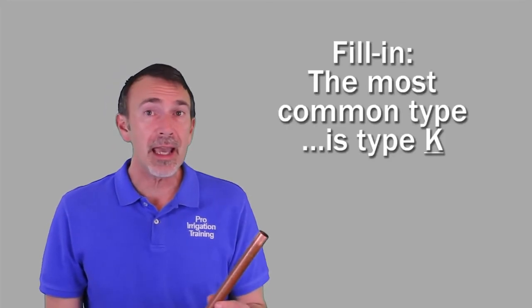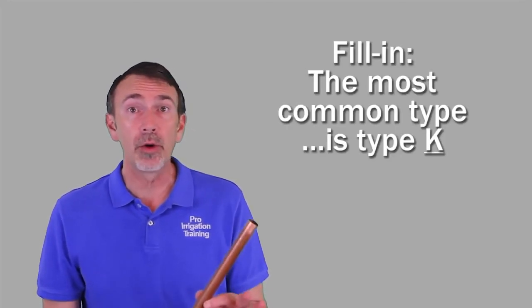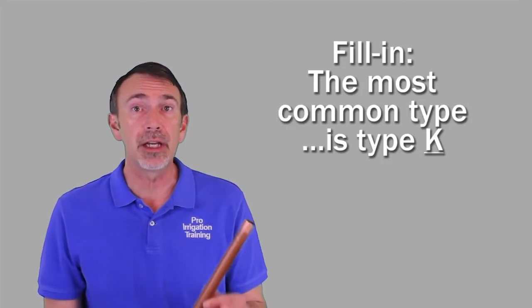The next major piping system that we're going to discuss is copper tubing. There are three different types of copper tubing that you may possibly encounter. It's types K, L, and M. Type K is the kind that you're most likely going to encounter as an irrigation technician, and it's the thickest wall of the three. That's what I'm holding now, a stick of type K. It comes in sticks and rolls.